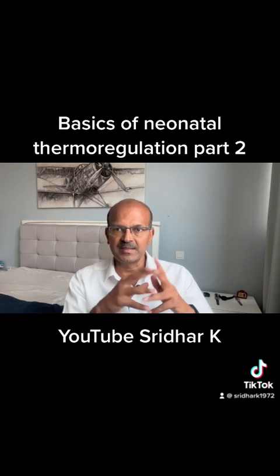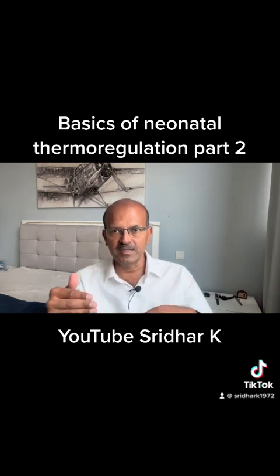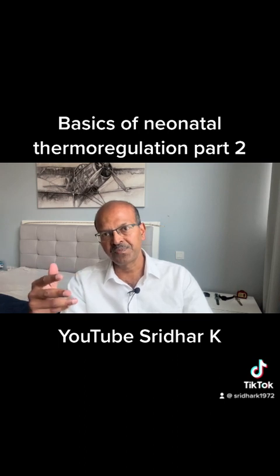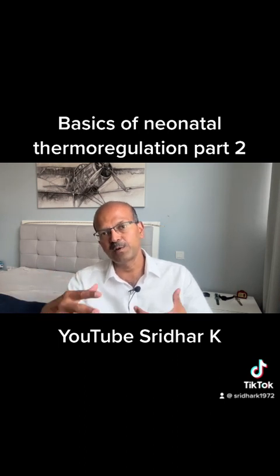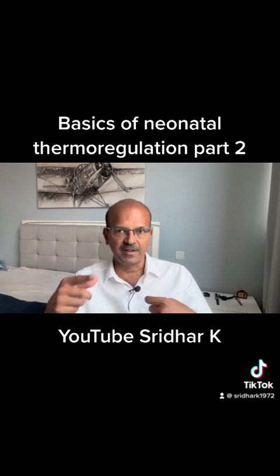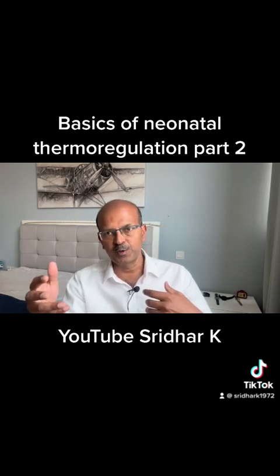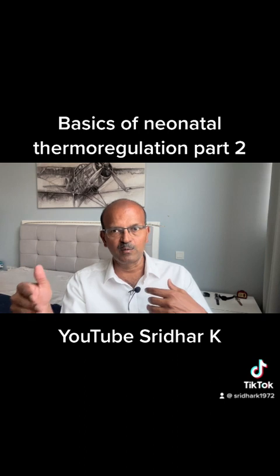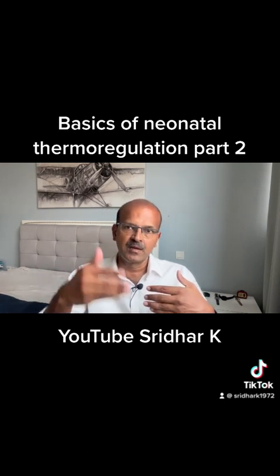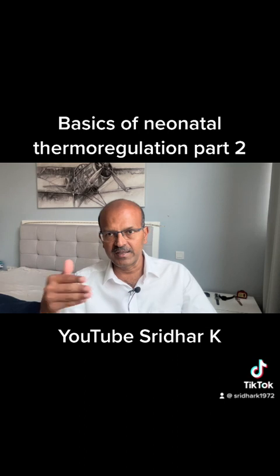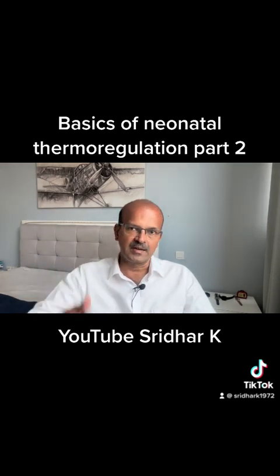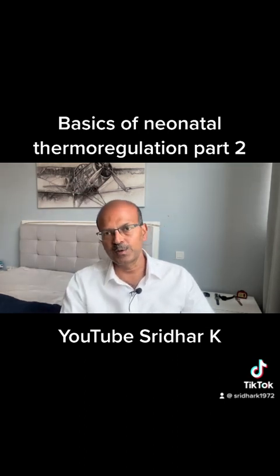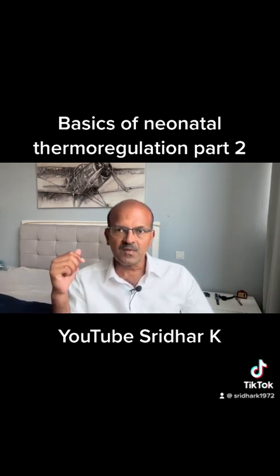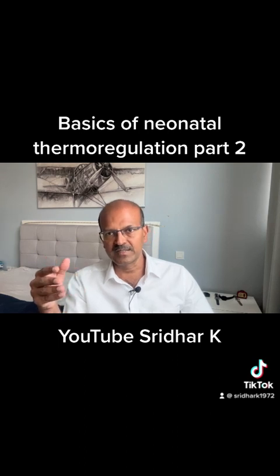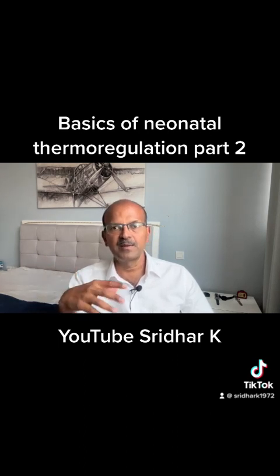In the premature babies, as I said, the incubator is preferable. The incubator works on the principle of convection. So inside the incubator body, you have the heater element and you have a fan. The more sophisticated incubators are double-walled. Most of these are double-walled, and they also have an air boost technique where if you're opening the doors of the incubator, you press a button and it gets a curtain of heated air, so you don't lose temperature to the external environment.